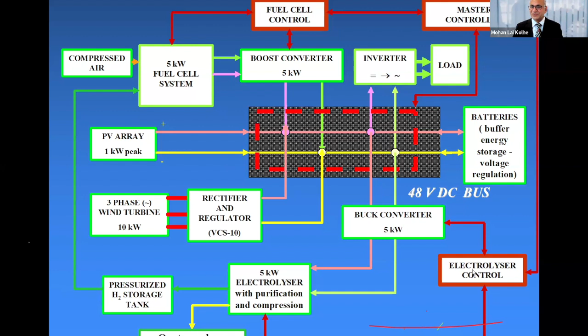I was talking about the DC bus, and on the DC bus we have to maintain the energy level. We need short-term energy storage on the DC bus for maintaining voltage sustainability, and for calculating the energy level at the DC bus to decide the operation of the electrolyzer and fuel cell, so we can avoid simultaneous operation. These parameters are monitored by the master controller, which takes decisions and sends information to the electrolyzer controller and fuel cell controller.